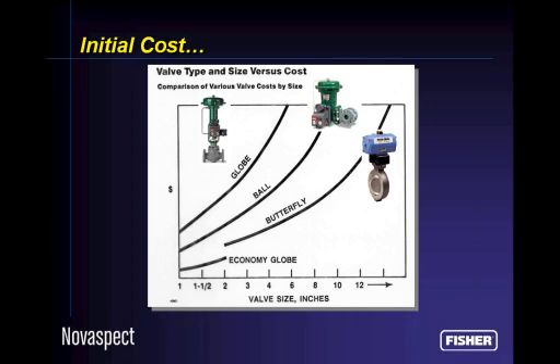We want to use the right valve that provides the level of process control accuracy that you need to stay on set point and keep you profitable. And we don't want to spend any more of your money than we need to in order to accomplish that task. And we certainly don't want to cheapen up on the valve that we use in a process that's critical. So valve manufacturers might sometimes suggest, yes, you can save money with a butterfly valve, but this application requires something more appropriate to good flow control. So listen to your valve manufacturer in these issues.